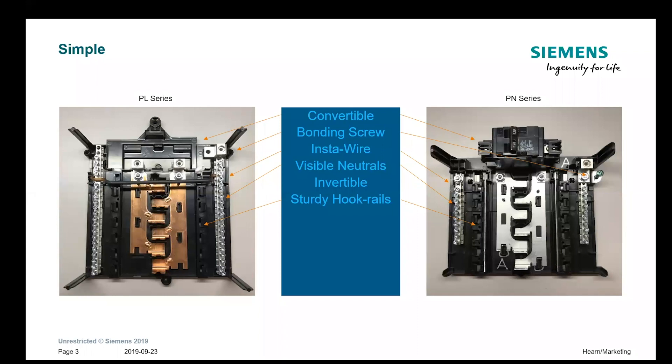The first thing our engineers did when designing this new load center is they kept it as much like the original series as possible, retaining all the positive features. The convertibility of the PL series from main lug to main breaker or main breaker to main lug is retained in the PN series. There's the bonding screw, the insta-wire with the neutral bars and ground bars with screws already backed out, and the visible neutral so when you're looking down on the load center you can see where your neutrals are landed. Both the PL and PN series are invertible and both utilize the sturdy hook rails.